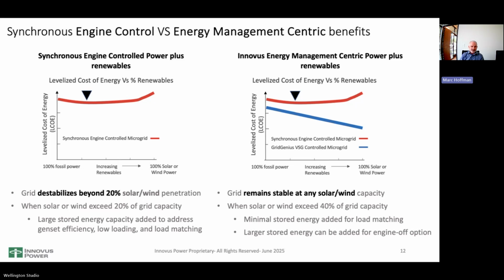So at first you start adding solar and wind, and your cost starts to drop, as you would hope, because you're not burning as much diesel. But I alluded to a 20% law, because once you get to about 20% capacity of solar and wind on that grid, the diesel gensets can't keep frequency within sound limits, and voltage starts to drift, and now you're risking an outage.